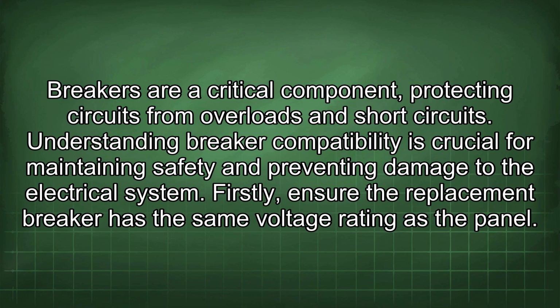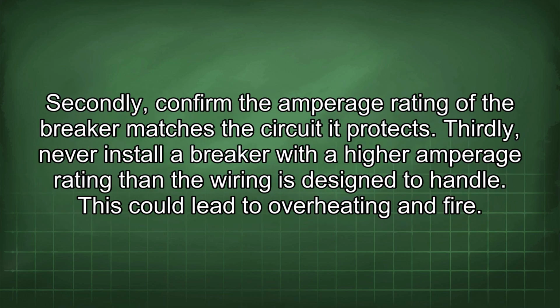Firstly, ensure the replacement breaker has the same voltage rating as the panel. Secondly, confirm the amperage rating of the breaker matches the circuit it protects. Thirdly, never install a breaker with a higher amperage rating than the wiring is designed to handle. This could lead to overheating and fire.